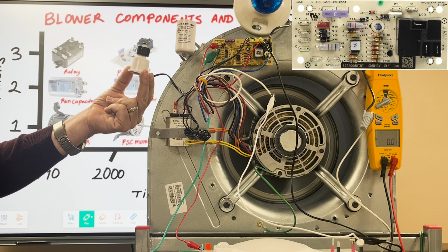And this is a long time to wait when you're just looking at it. So we always recommend get a timer out, and even if it's been running for a while, just so you can confirm, hey, listen, this thing has been running too long. I've got my stopwatch out. It's been 5 minutes. If that's the case, then your relay is stuck in the closed position, which does happen on these boards, and you just replace the board if that happens.